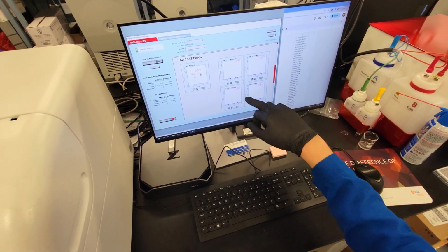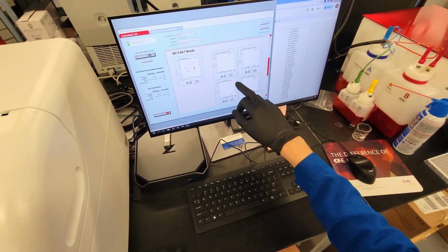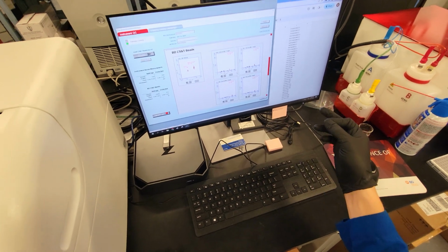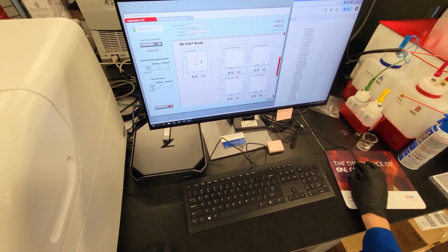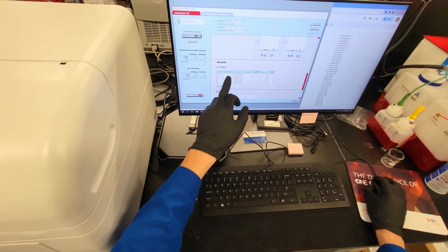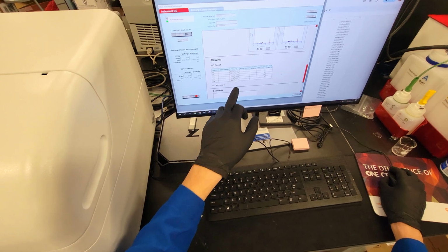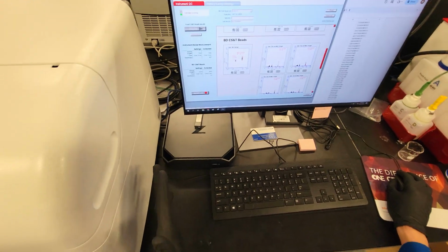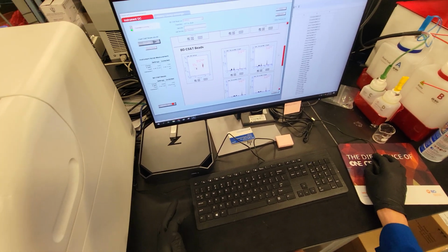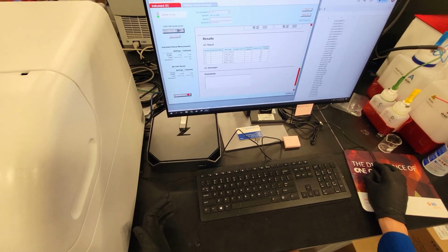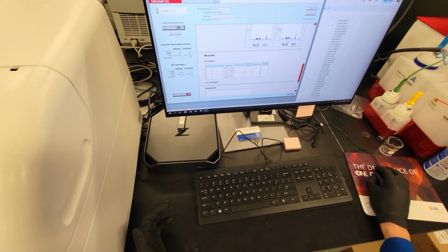And then it's also measuring on the 4 different detectors. So there's FL1, which is where we put our 533 nanometer filter, and we'll switch it to the 510 in a minute. But there's also 3 other filters in here, so FL2, FL3, FL4. We can scroll down, and once we get the report, it will add up all of the counts that it got in those ranges and say if it's within the range. So our machine pretty much always, and you can see this is live, it's counting them right now and adding to the regions. But our machine always overcounts a little bit on the forward scatter of the beads in this range in particular.